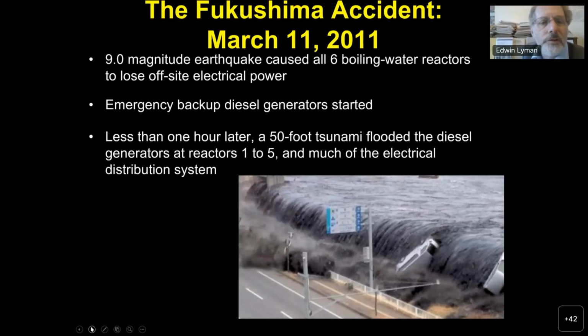Sorry. Yeah. So quickly, Fukushima was a station blackout, a prolonged loss of all AC power, and that's because it was first initiated by a massive earthquake, which took out the offsite power lines to the plant. All the backup diesel generators started, but the tsunami that was generated flooded the site less than an hour later, and that caused a massive power failure, disabling all the electrical systems, including the backup diesel generators and most of the batteries. You can keep scrolling.